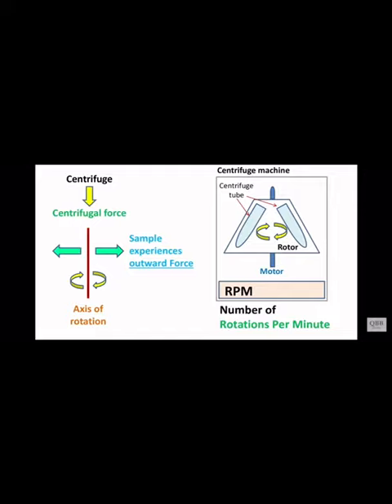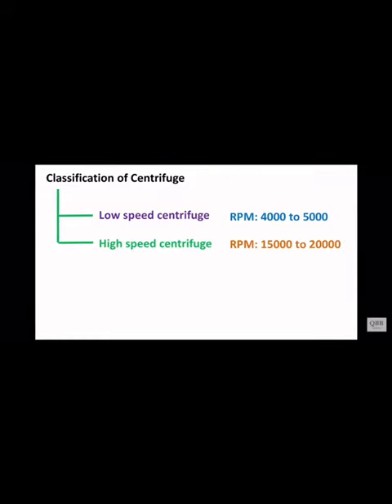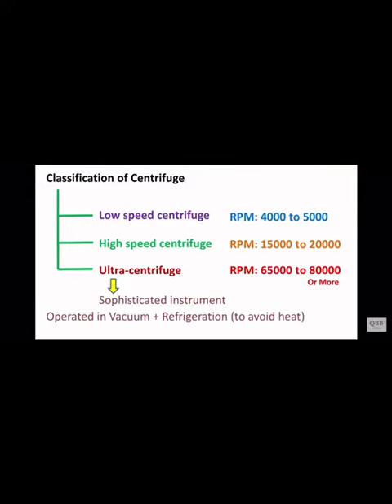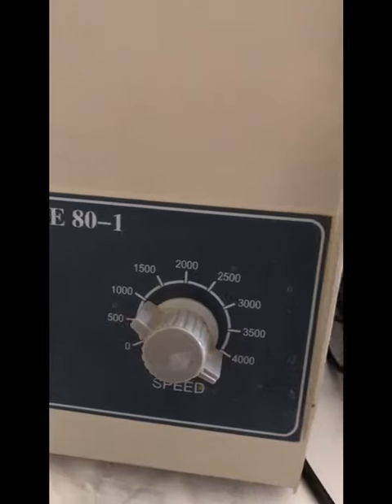Depending on the RPM, centrifuges can be classified into several types. The first one is the low speed centrifuge that operates from 4000 to 5000 rpm, and then there comes the high speed centrifuge which operates from 15,000 to 20,000 rpm, and the last one is the ultracentrifuge which operates from 65,000 to 80,000 rpm or more. The ultracentrifuge is also a sophisticated instrument which is operated in vacuum along with refrigeration to control heat generated at such high rpm.